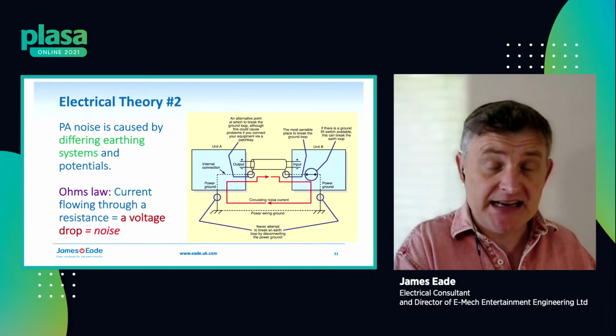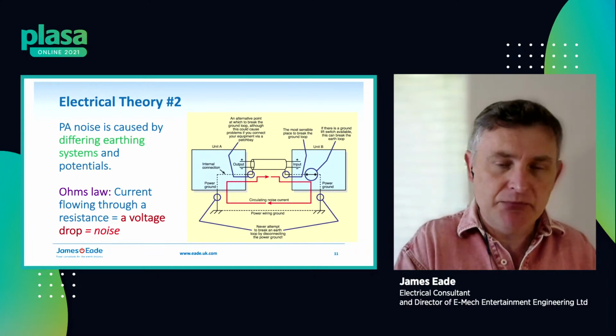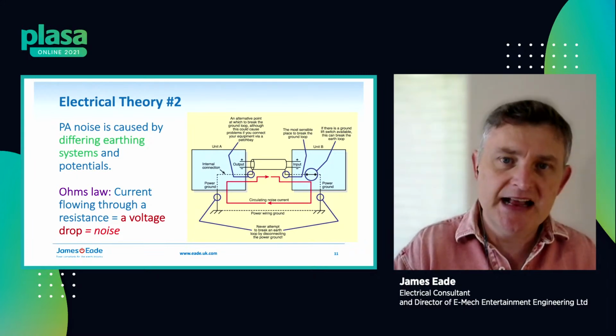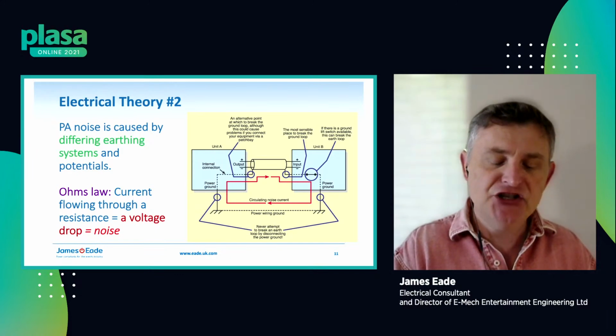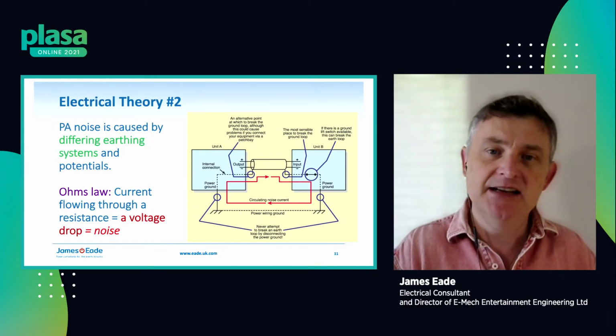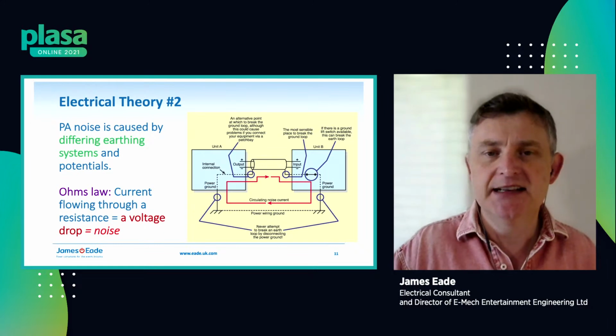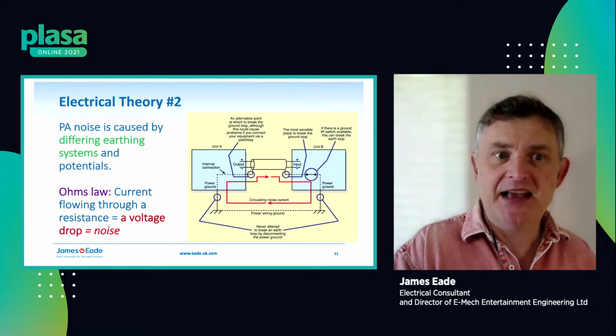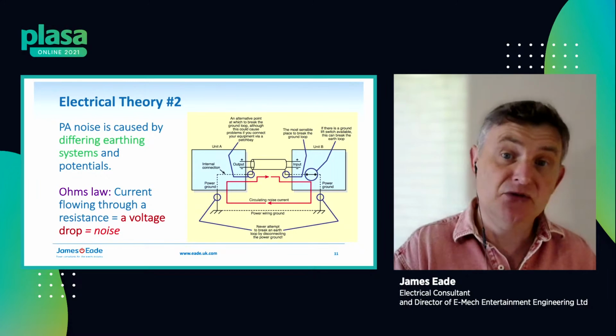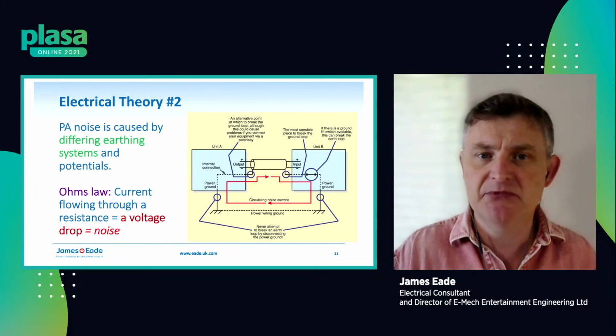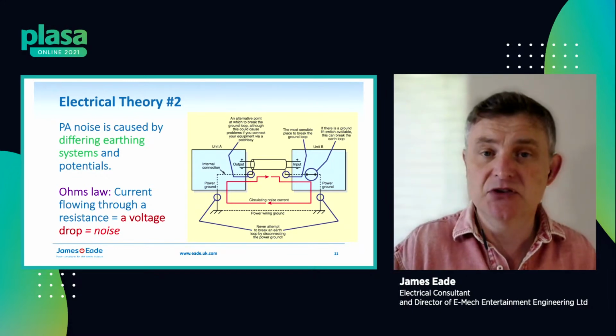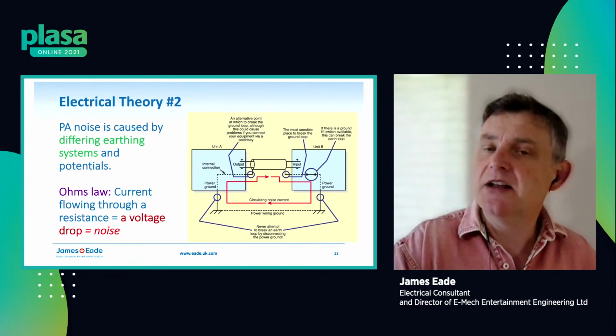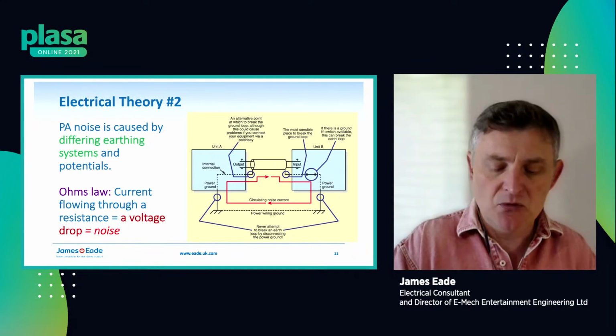But from an electrical safety aspect, you can run cables in the same enclosure altogether, but the insulation of all the cables has to be rated for the highest voltage present. So if you're running mains and audio together, the insulation on the audio cable should be rated for 400 volts, for example, or more, to make sure that if there is a fault, then the audio cable is going to be suitably protected.